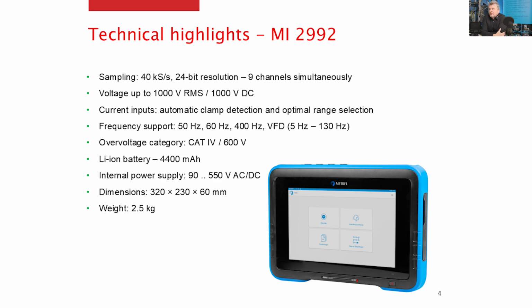DC voltage and current is directly supported, with 50 or 60 Hz frequency support, where it is also analyzed as a special case. Based on a specific design, we are enabling category 4 600 volt, which enables the installation of the instrument directly in a transformer station in a category 4 environment.